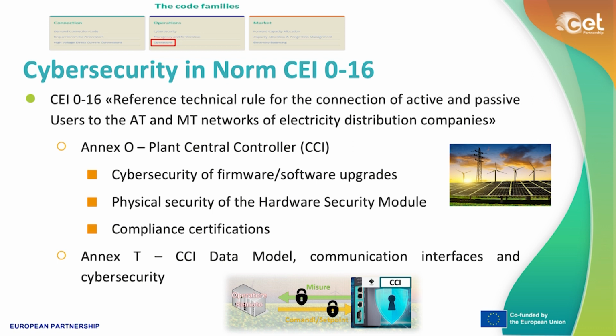In detail, the Italian norm 0-16 includes cybersecurity requirements in two different annexes, Annex O and Annex T. In Annex O, we have defined the procedure for performing firmware and software upgrades in a secure way, preserving cybersecurity during these activities. We have also established requirements for the physical security of the hardware security module, one component of the plant controller, and prescribed specific compliance certifications. In Annex T, we have defined the controller data model, communication interface, and cybersecurity profiles.